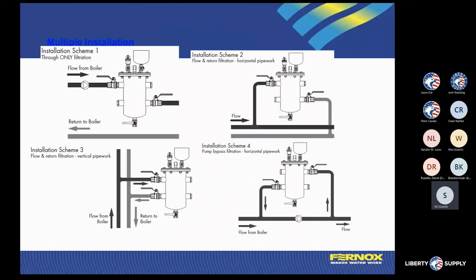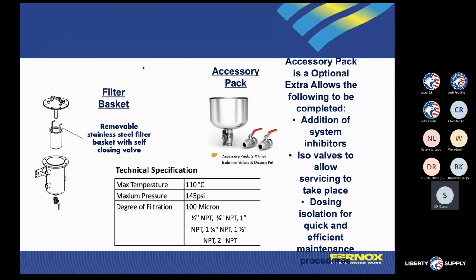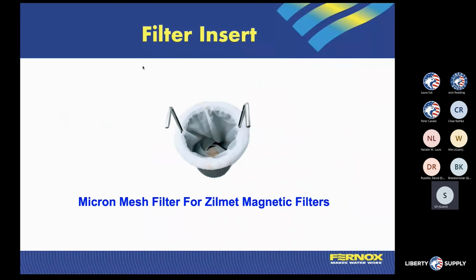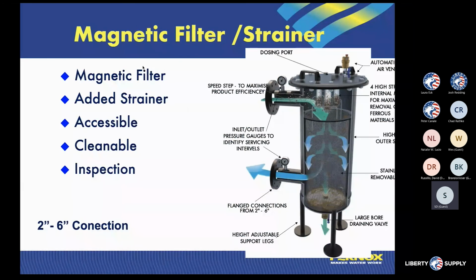Because we can do multiple filter positions and we have multiple size systems, going from a 1/2 inch to a 6-inch style magnetic filter, there are options out there for all different types of systems, depending on what you're trying to get to. And again, there are different accessories. We have our strainer, but we also can have a dosing funnel and additional ball valves to make that process simpler. And then, like I was talking about earlier, we can also put in a filter mesh to deal with the fact that we may have sediment that's finer than the basket strainer, which is 100 mesh, can capture. So if that's the case, we can also add that to the puzzle as well.